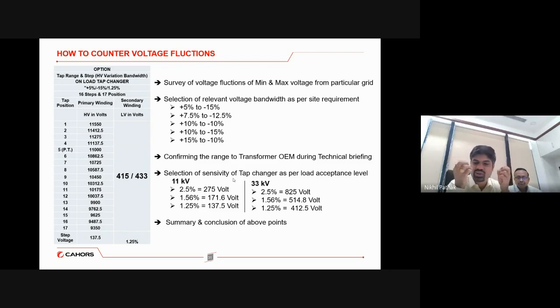And as an energy audit also, we have to see whether the given tap range is in line with the fluctuations of the grid or not. Secondly, after the tap range, the sensitivity also has to be defined very properly as a requirement of the customer.